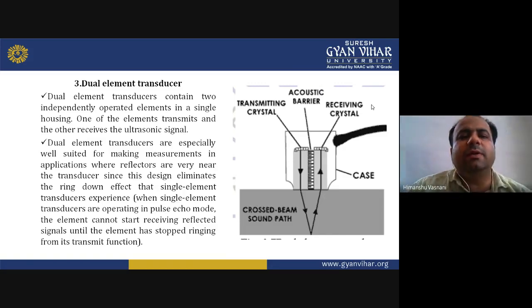Let's start with this. Dual element transducers contain two independently operated elements in a single housing, as we just saw in the diagram. One of the elements transmits and the other receives the ultrasonic signal. You can see the transmitting crystal in the diagram. Now, dual element transducers are especially well suited for making measurements in applications where reflectors are very near the transducer, since this design eliminates the ring down effect that single element transducers experience.